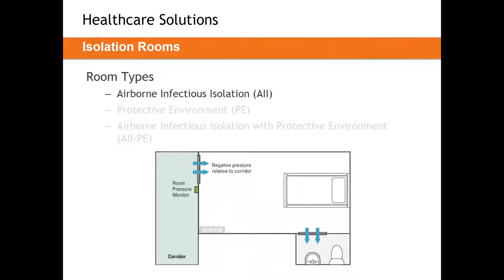In an airborne infectious isolation room, we house and treat patients who have communicable diseases — tuberculosis, smallpox, influenza, or measles, for example. We can't put the rest of the hospital at risk, so we need to isolate that airflow. In an AII room, we negatively pressurize the space. Air will constantly flow into that room from the rest of the building, with a large proportion flowing in around the doorway.